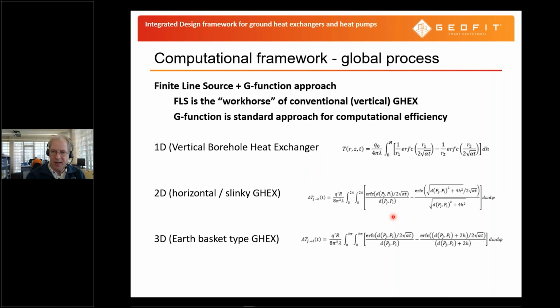So our challenge was to develop all the G functions for the analytical functions for all the different ground heat exchangers. And what we've been using is the finite line source equation, the finite line source analytical solution, which is basically the workhorse for ground heat exchanger design. And fortunately, of course, for the 1D case, the vertical borehole heat exchanger, this equation already exists for a long time and is well known. And even for the horizontal and the ring type of heat exchanger, it has been developed and published, for instance, based on research from the United States. So what we have done mainly is implement these two in our engineering tool and then add it from 1D to 2D to 3D, the earth basket type heat exchanger, in the same standardized methodology.